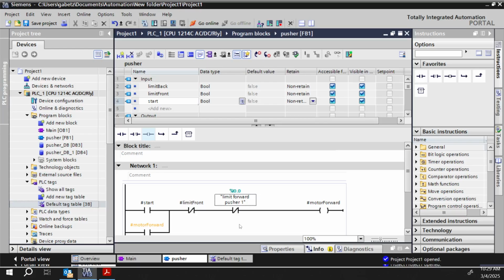All right. So, like if you had an e-stop button, that would be a great place to put it. You could just pop your e-stop in there, say if this button's pressed, nothing's allowed to happen. And again, that's hard-coded in everything. It doesn't matter which conveyor it is. If I hit this e-stop, I want everything to stop in this facility. So hard-coding that inside these functions, perfectly fine. If you're using them just for organizational purposes, everything's going to be hard-coded here. Perfectly fine. Right? But I say, try to use these how they're actually supposed to be used.